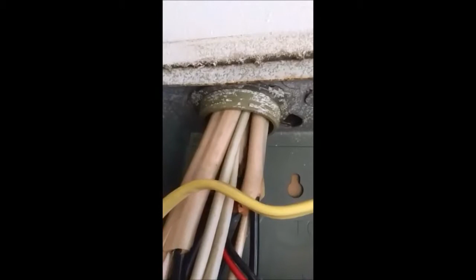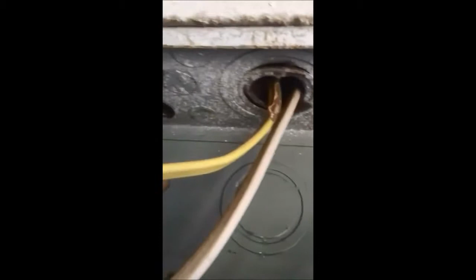This has none. You can already see that there's some damage to the wire, so we need to get that taken care of. Another thing you see here is some empty knockout holes that are not being used. We need to get those filled up and sealed off, so that sparks don't fly in and out of the panel, or anything else for that matter comes in and out. We want to keep that sealed off as best we can.